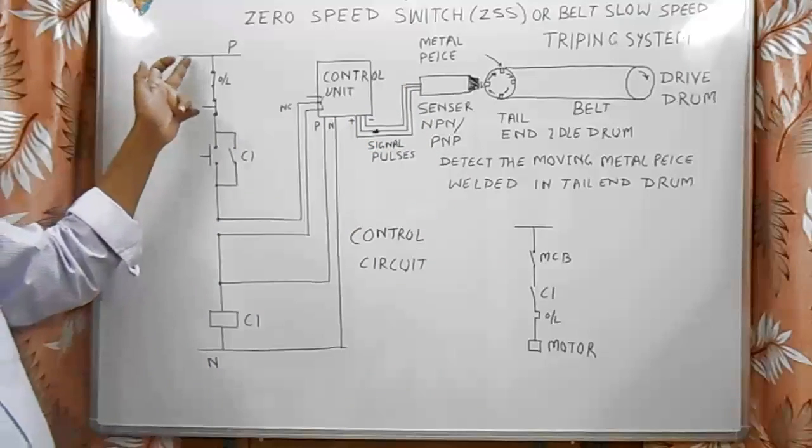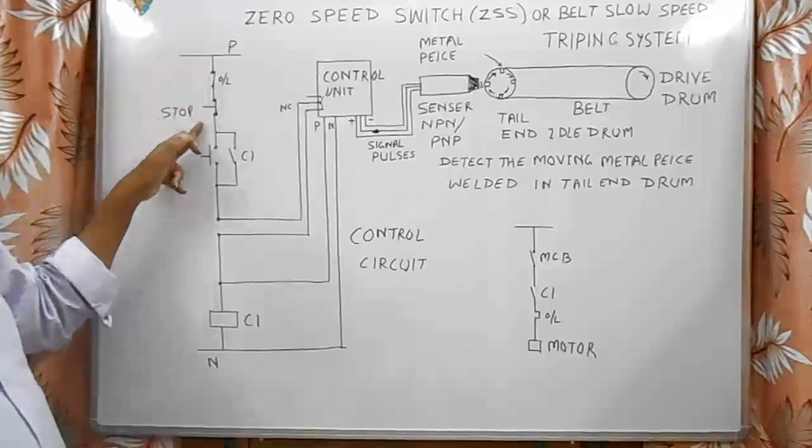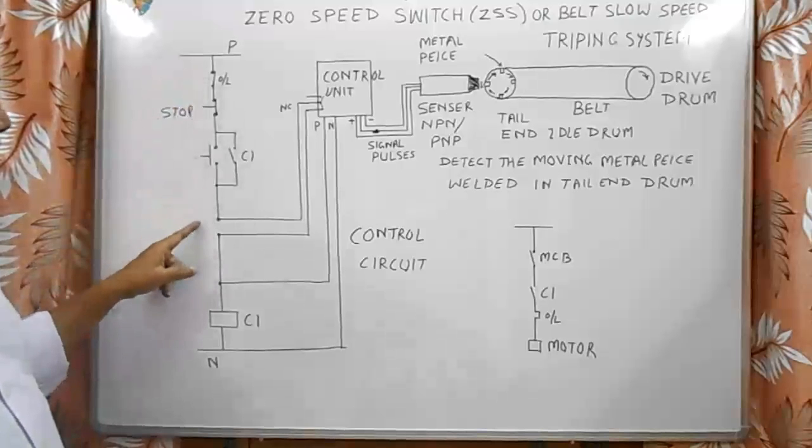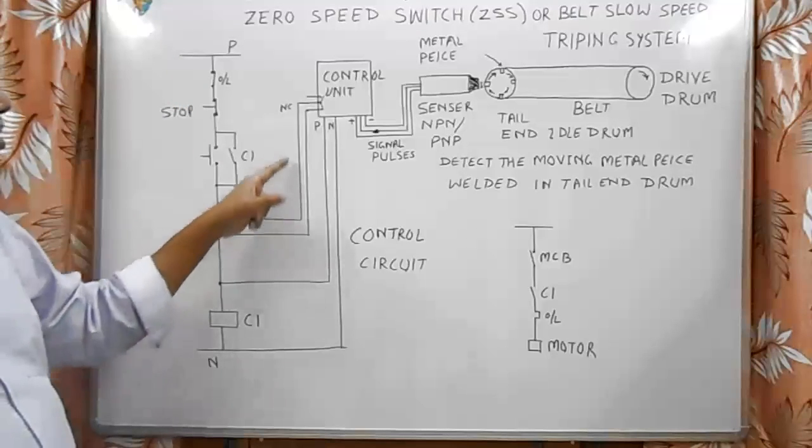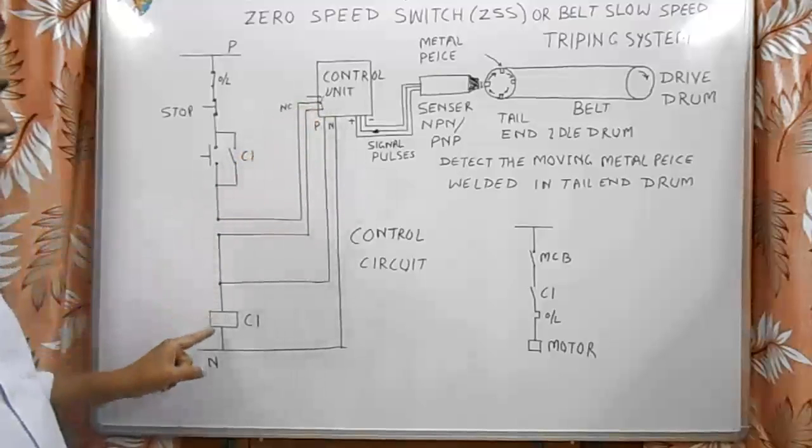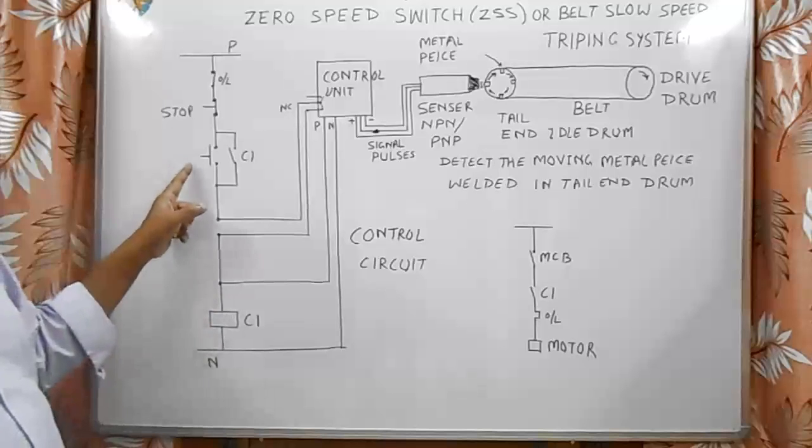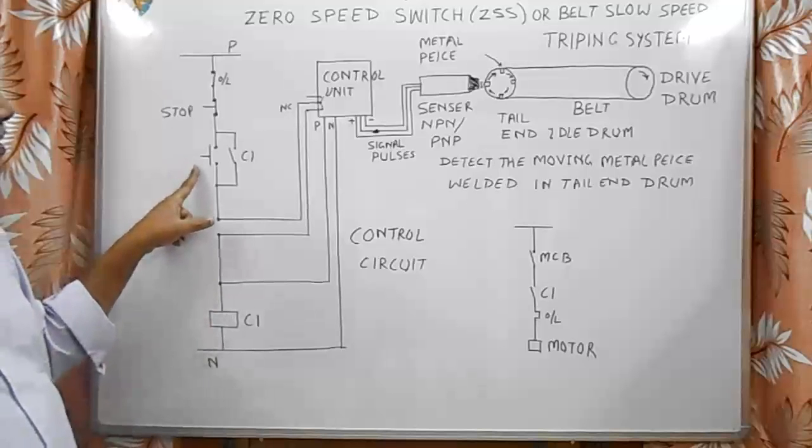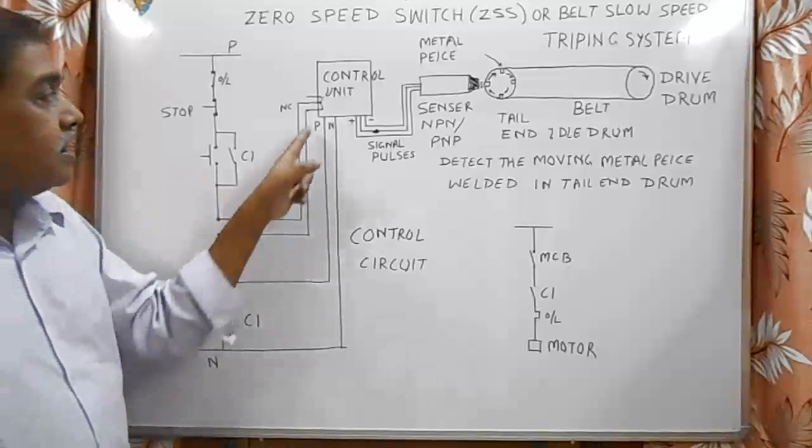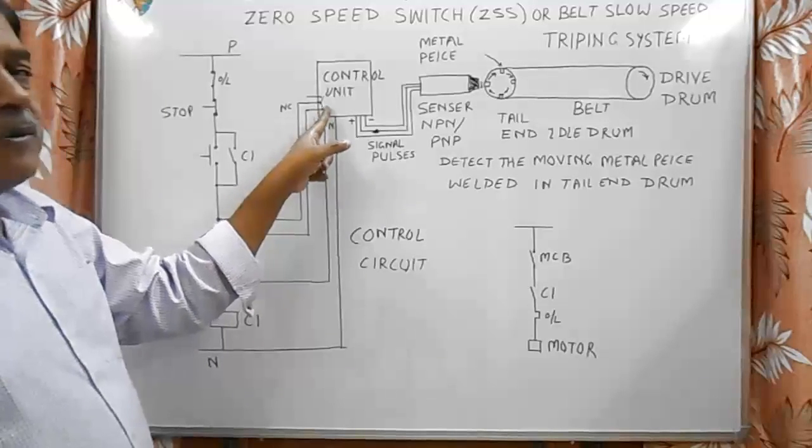In the control circuit, phase R goes to one terminal, then from the stop button, then start button, and from there to this interlocking contact of the control unit. From there it returns back to the C1 contactor coil. When we press the start button, this contactor picks up and C1 closes. This contact remains closed till 15 seconds till the belt picks up speed.